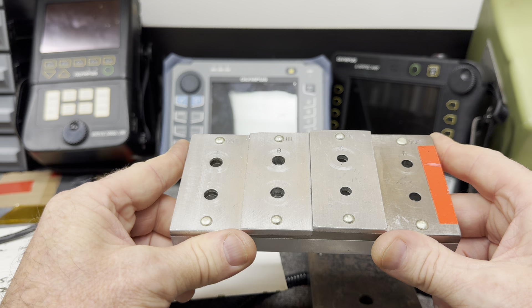I'm primarily a tubing guy, and tubing inspection is more difficult than surface. Maybe if you're a surface guy, you don't like that, but seeing it on both sides, there's just a lot more components to tube testing. First of all, if you're doing aircraft, you have the option a lot of times to go single frequency or dual frequency. But when you're doing tubing exams in the nuclear environment, you're always using 4 frequencies, and you're constantly flipping between those frequencies to separate variables. You want to use certain frequencies to confirm tube deposits, maybe fouling on the OD of the tube, to check for clogged flow slots in broach support plates, to confirm magnetite, to confirm whether something's ID originating or OD originating. Then you got your 2-channel mixes for suppressing one variable like tube support plate signals that could mask flaws.